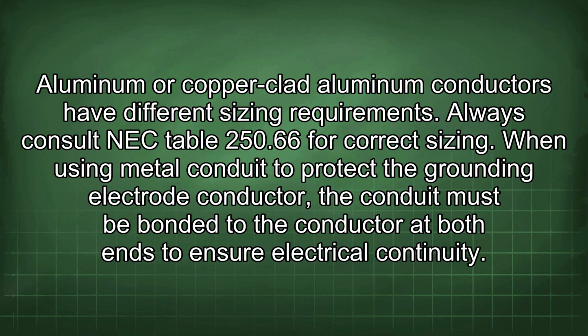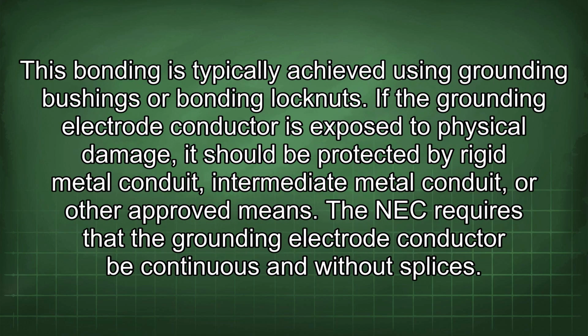When using metal conduit to protect the grounding electrode conductor, the conduit must be bonded to the conductor at both ends to ensure electrical continuity. This bonding is typically achieved using grounding bushings or bonding lock nuts. If the grounding electrode conductor is exposed to physical damage, it should be protected by rigid metal conduit, intermediate metal conduit, or other approved means.